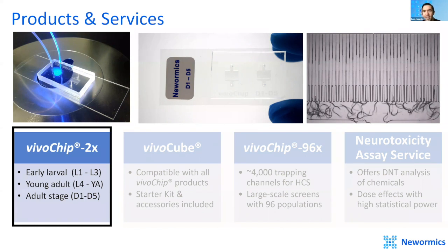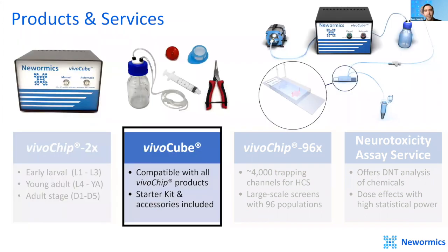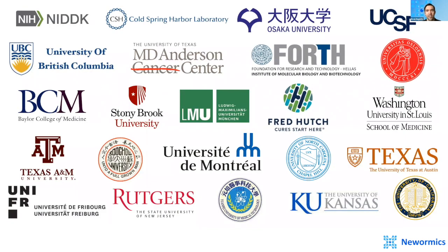We now have a wide range of VivoChips to study different age worms, from the earliest larval stage through day five adult. Don't worry if you're not equipped for large scale — we have developed something very unique to meet the needs of university labs: the VivoChip 2X. It uses the exact same microfluidic technology, but with two wells instead of 96. The VivoChip 2X comes on a number one glass slide, has two independent immobilization devices each with 40 trapping channels, and is compatible with inverted and upright microscopes using any magnification objective.